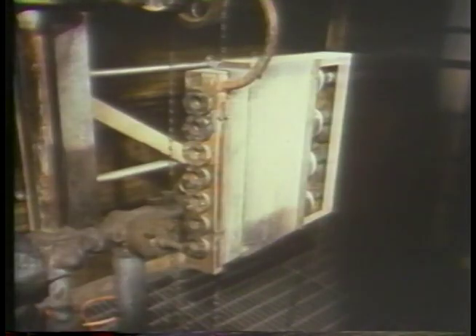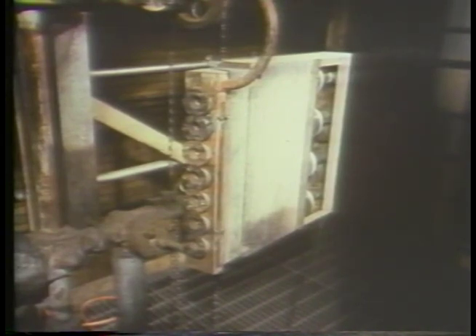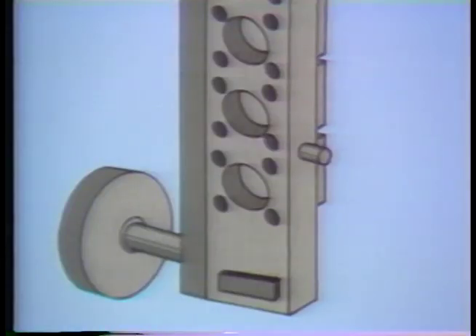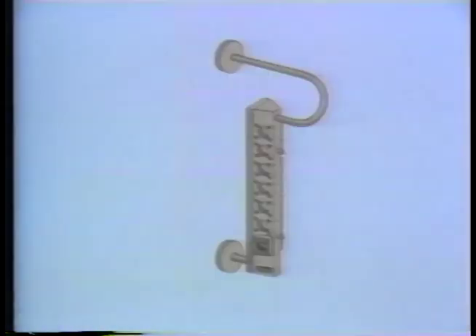The final type of gauge glass is the multiple-port gauge glass. Multiple-port gauge glasses are often used on high-pressure components such as boiler drums. A typical multiple-port gauge glass has a slightly wedge-shaped body with a series of round openings on each side, covered with thick pieces of glass held in place by cover plates bolted to the body.